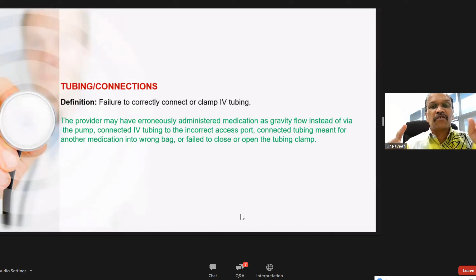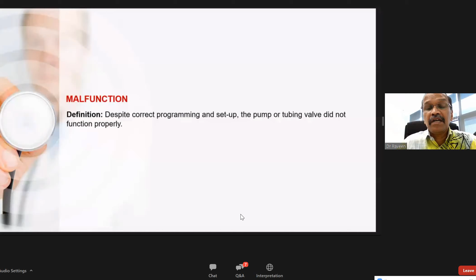Malfunction of the pump. You might have programmed it well, you set it up well, everything is correct, but the pump did not function. I'll give you an example. The patient was put on an infusion of furosemide, and you had programmed it, say, for 5 mils per hour. But when you checked, you noticed that the pump was actually delivering more than 5 mils per hour, although your setting was correct. So that's a malfunction of the pump. You should stop using the pump immediately and send it down to your biomedical department for checking, or refer it back to the supplier to come and check the pump.